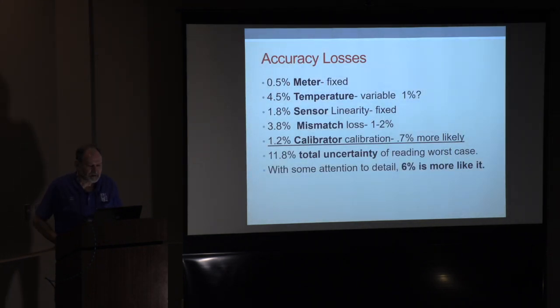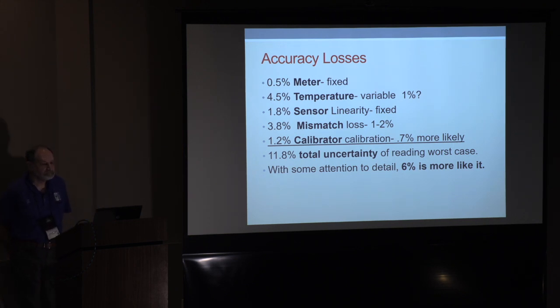Okay, so here's a list of uncertainties. 0.5% for the meter is fixed. 4.5% for temperature. I think you can get that down to 1%. Sensor linearity is 1.8%. I would measure that to make sure what the actual uncertainty was. Mismatch loss, I think you can get to 1 or 2%. And the meter calibrator is more likely 0.7%.